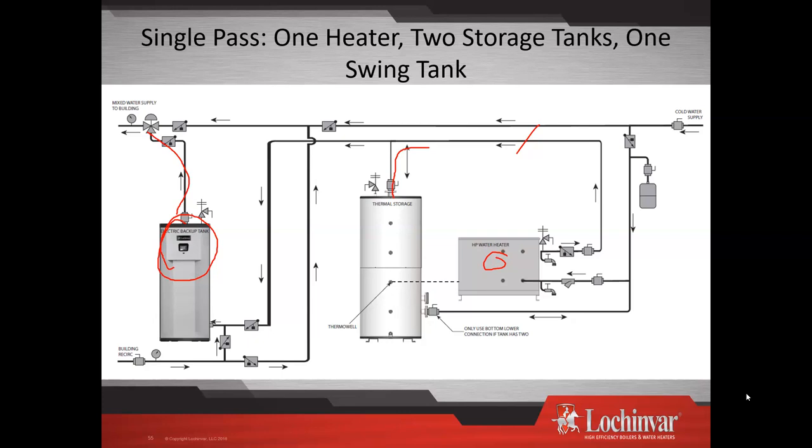So if you have a moderately small unit as your swing tank, then it's a swing tank. It can also serve other functions if it's large enough. It can be a backup if your heat pump goes down or is unable to keep up. If the heat pump's running but can't keep up with the system load and you've already drawn down your entire thermal storage, then this acts almost as a peak shaver.